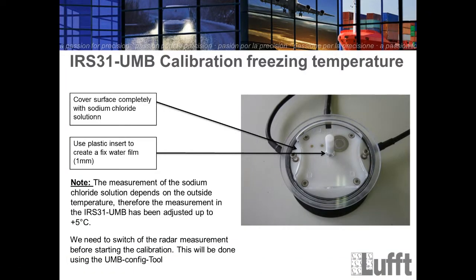So let's go back. Again, here are the notes, right? You have to cover the surface completely with the sodium chloride. You have to use the plastic insert to create a fixed water film. Then you can start a measurement. The notes are very important. Here, please check the notes again. The measurement of the sodium chloride solution depends on the outside temperature. Therefore, the measurement in the IRS31 has been adjusted up to +5 degrees Celsius. So you have to do this check under outside conditions of 0 up to 5 degrees Celsius.